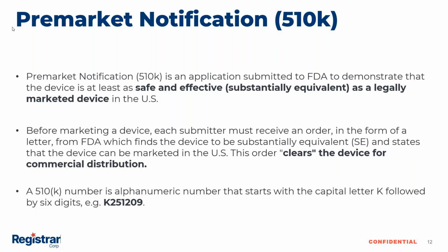Most likely companies are using a competitor device that is as close as possible and that they know very well. In some other cases, you might also be able to use a 510K that you had previously, maybe a couple of years earlier, and now you have developed a new device, or applied new technology, or extended the intended use of a device. Then you might be able to use your old 510K as the comparison device for this 510K application.